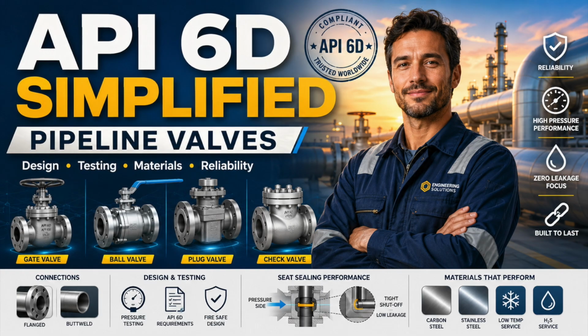An undersized actuator may fail to move the valve. An oversized actuator may damage the stem or internal parts. The objective is not maximum torque. The objective is reliable, controlled operation without mechanical overload. Hydrostatic testing is essential, but a past test does not prove long-term reliability. A shell test demonstrates pressure boundary integrity under defined conditions. A seat test demonstrates leakage performance under defined pressure, direction, and duration. It does not prove resistance to debris, thermal cycling, aging, corrosion, misalignment, poor installation, or years of inactivity.